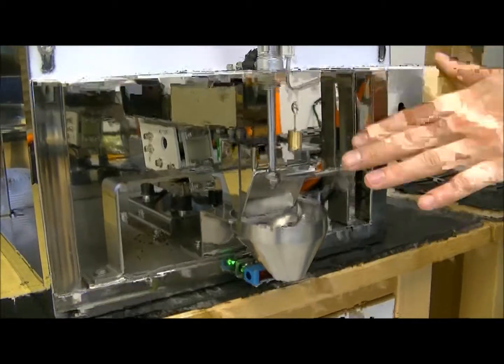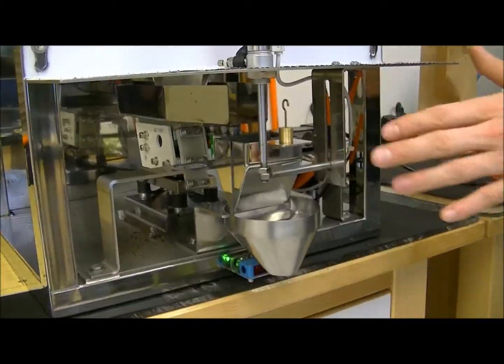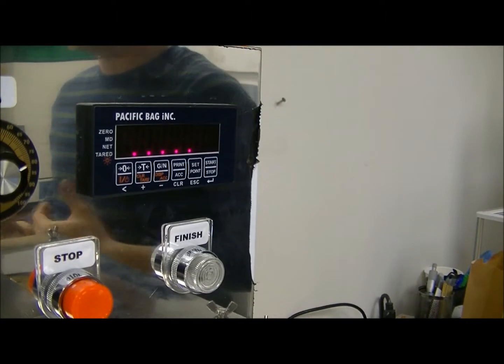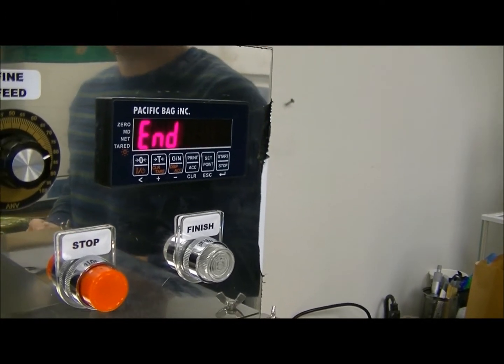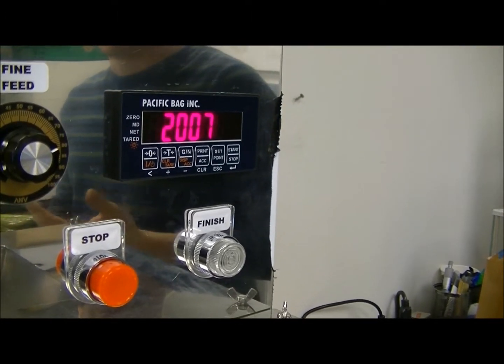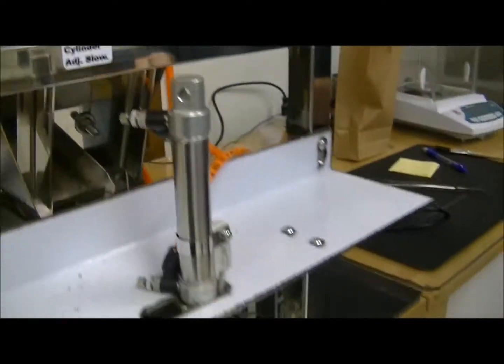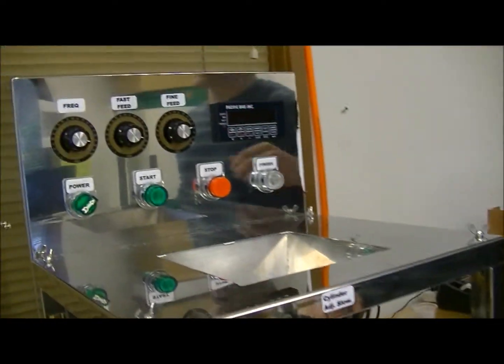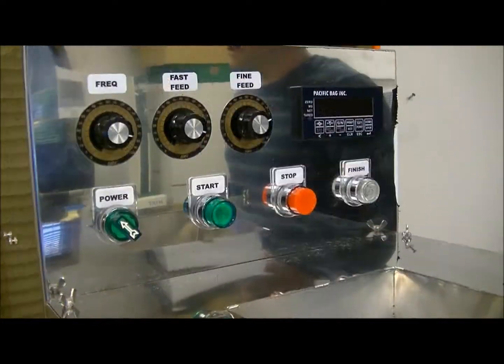Okay, so with the 10 gram weight on the weighing bucket and 10 grams on the display, we'll hit enter and the machine will read that weight and then say end, and we'll go back to the calibration screen. At this point, we can turn the machine off so that we can take it out of calibration mode.